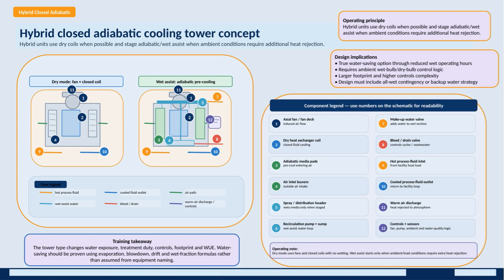The hot process fluid enters from the facility heat load, and once cooled, it is returned to the facility loop with warm air discharged to the atmosphere. Finally, all these processes are managed by integrated controls and sensors that monitor fan operation, pump activity, ambient conditions, and water quality to optimize performance and ensure efficient, reliable heat rejection with minimal water use.